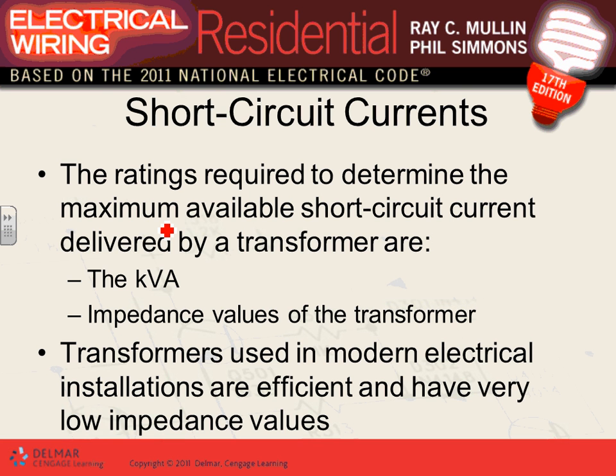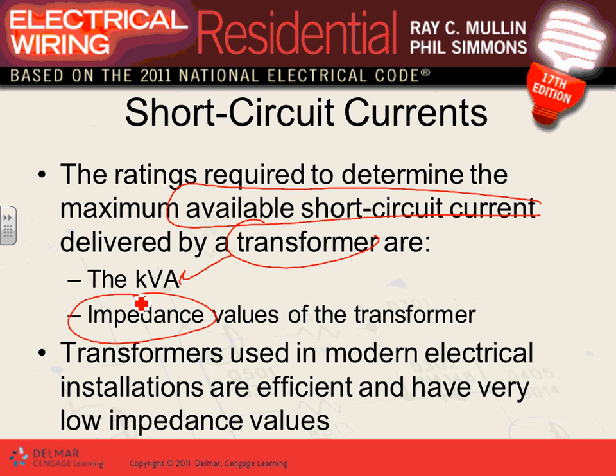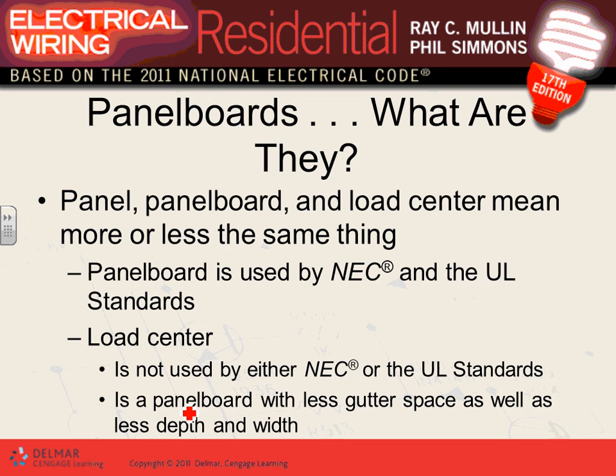Short circuit calculation: when you do a short circuit calculation for the system, you need to find the KVA of the transformer and the impedance of the transformer, plus the impedance of all equivalents — that tells you how much current will be available at a short circuit. Because of energy efficiency and green buildings, transformer impedance is becoming very low, meaning higher available short circuit current.